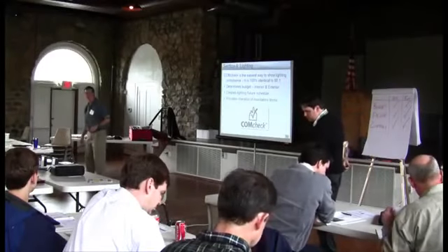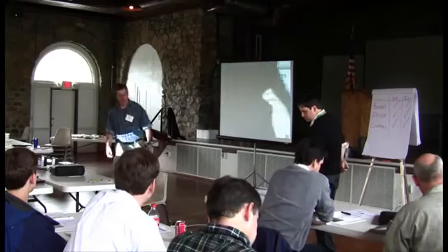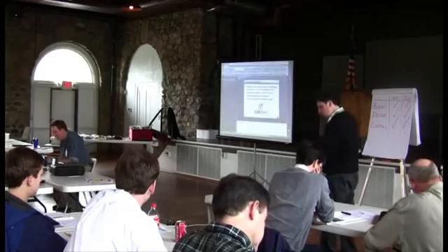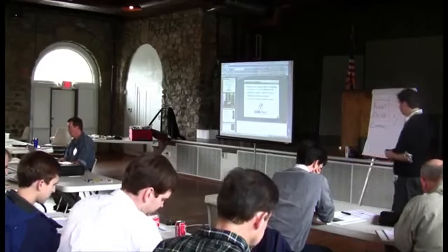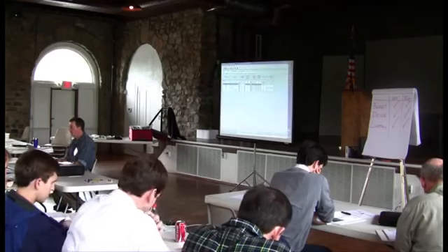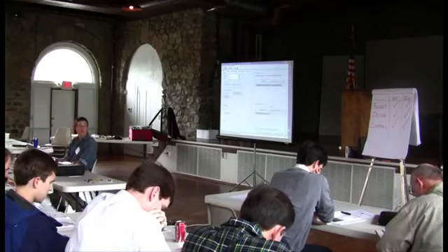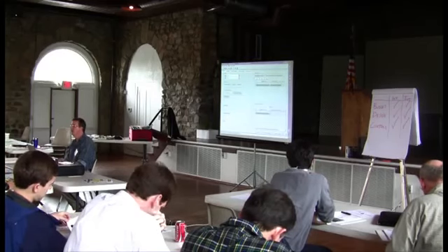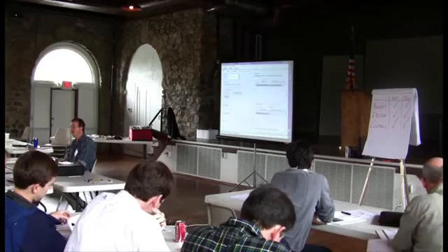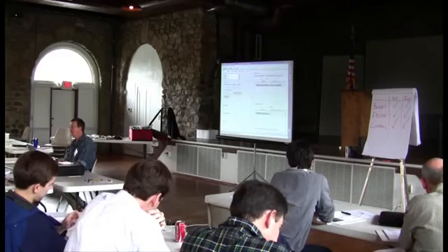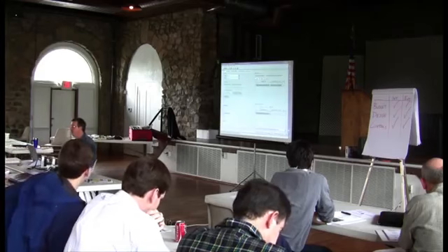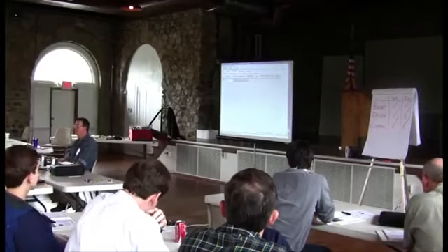All right, the last thing that we really want to show is how to use COMcheck to do this for you. So let's see if I can pull some up here. So COMcheck. Again, I hope, can you kind of see this reasonably well? On the first page up here, I said we're going to use the building area method. The first page just says I've got a retail store. Here's the square footage. Here's the lookup, and it calculated that my budget is 5250 watts. That's what I get for lighting up my building.